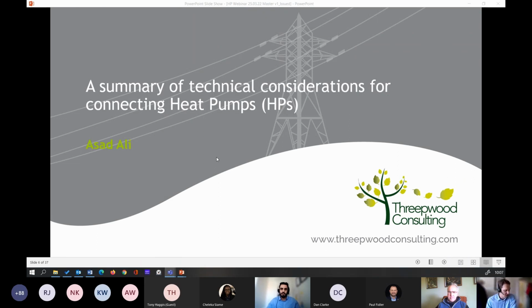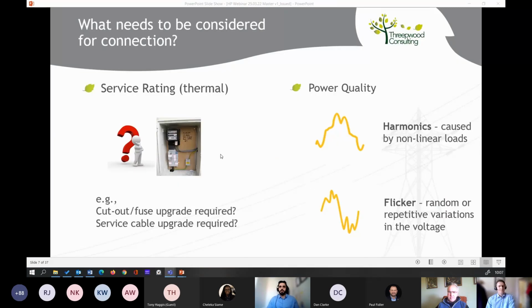Asad, first question is really what's the most important thing about connecting a heat pump? What are the headline considerations? So the first thing we've got to consider is the service rating. That's because we're adding heat pumps to the current network, and that's going to draw more current from the network, so we've got to be wary of what the cutout or fuse can handle.